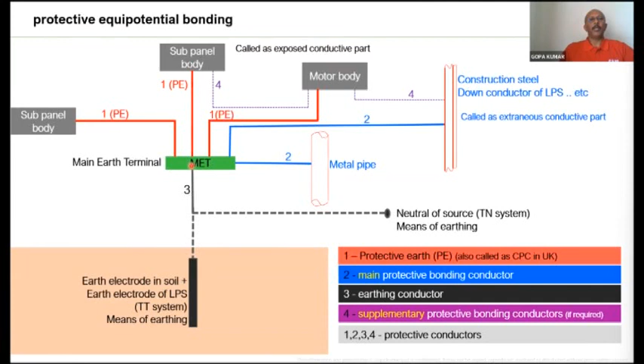Every metallic object in your building, such as the metal pipe, the structural steel materials, the aluminum facade, and everything, must be interconnected in a typical fashion. The whole story of earthing is how you are making this interconnection. Earthing has very little to do with the earth electrode in soil. The last part: inspection and testing.